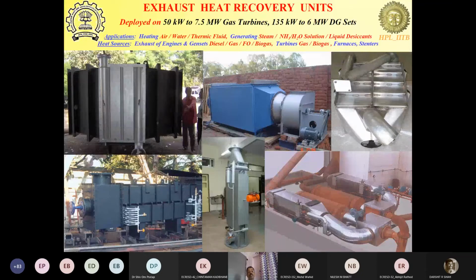Okay, then we would move on to exhaust heat recovery. Now, there might be gas turbines installed in a facility, or there might be gensets installed in the particular facility, and there might be exhaust heat available. So we can generate various utilities from the exhaust heat. We can heat up air for process heat, process applications. We can heat up water.